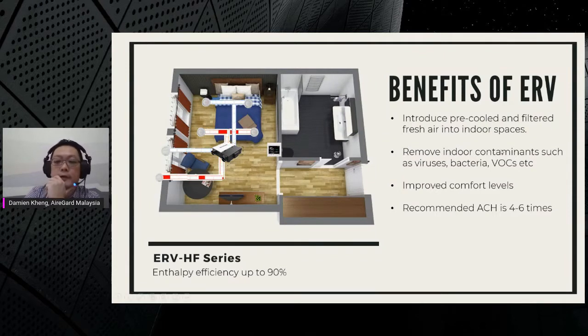It is also highly effective in removing indoor contaminants, because as you dilute the air, you are basically changing the air indoors, which dramatically improves indoor air quality. The WHO Annex 3 document recommends an air change rate of about 4 to 6 times per hour.